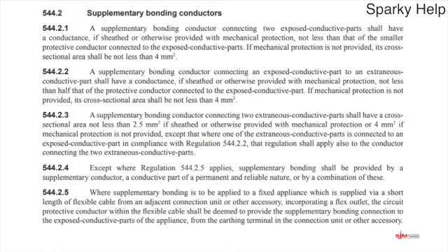So here is the set of regulations that apply to supplementary bonding, and there are 5 of them really. But probably the most common one that people are aware of is that you can get away with having just 2.5 between exposed conductive parts, providing it is with mechanical protection. Without mechanical protection, you can get away with a 4mm. However, in some cases it does depend on what conductors are connected to it. So if you have live conductors going into something, then the bonding is based on the size of those conductors as well. So let's look at number 1.